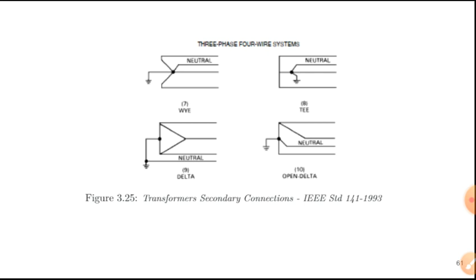According to IEEE Standard 141-1993, there are different connections for a 3-phase 4-wire system. The first is a Y-connected 3-phase system where the neutral point connects to the neutral line. It's also possible to use a delta configuration, though it's not practical and it's complicated — we call that the high-leg system, used for advanced purposes not covered in this course. There are also the T transformer and open delta configurations. We will be focusing on the Y 4-wire system.